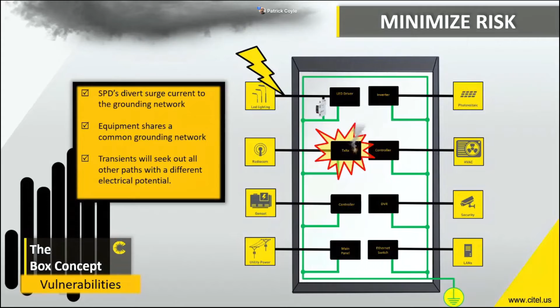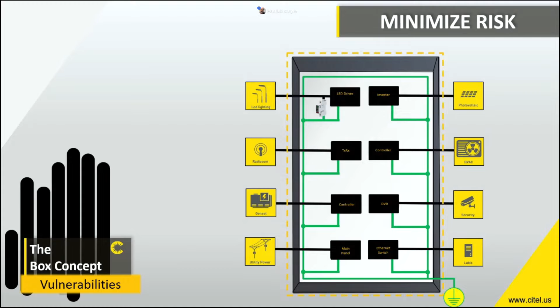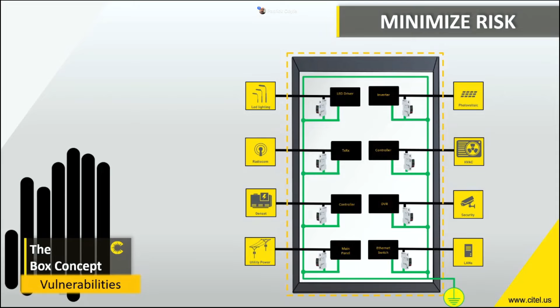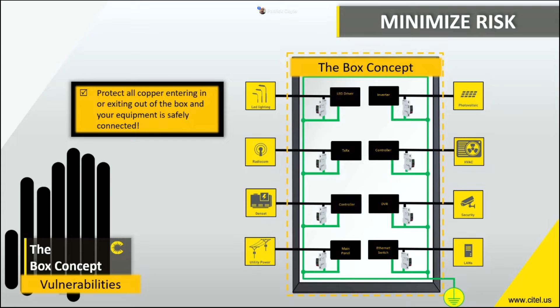Fortunately, the solution is easy. Simply draw a box around your equipment, your panel, your room, or even the entire building, and place a surge protector on all copper that breaks the box. So this will include all wires entering or exiting the box. We can't predict lightning and other surges, and once we try to figure it out, it'll definitely surprise us. The one thing we do know is that we can control only what we have control over. So that's how your points of entry are addressed within your cabinet, and how the power is protected. This is a guiding principle for the box concept. It's a practical tool to use, so please do use it. Like we said, simply draw a box around your equipment, and any wire, copper that breaks the box should be addressed with surge protection.